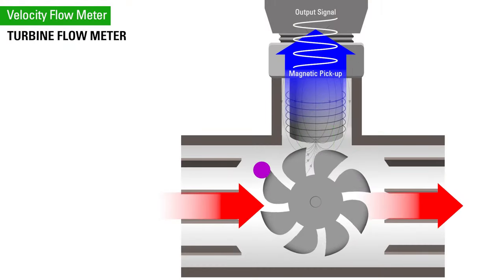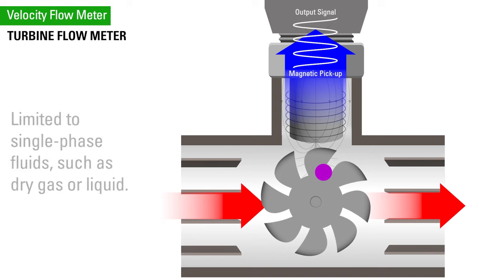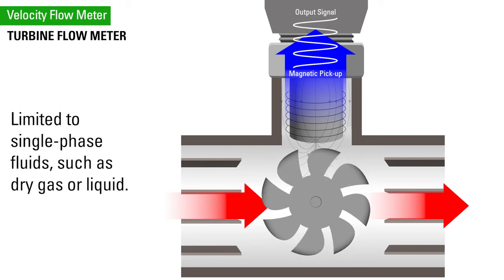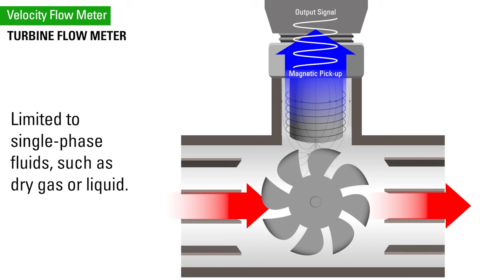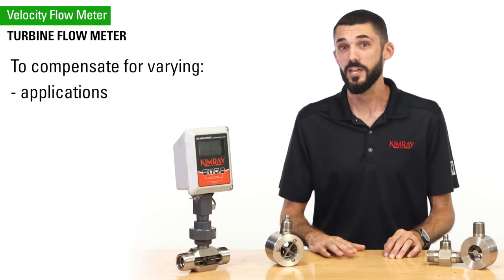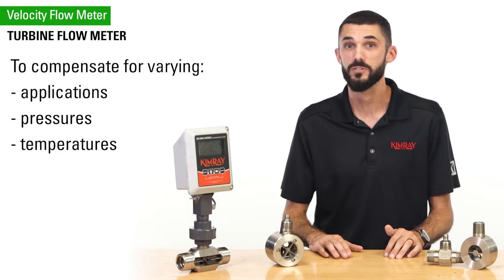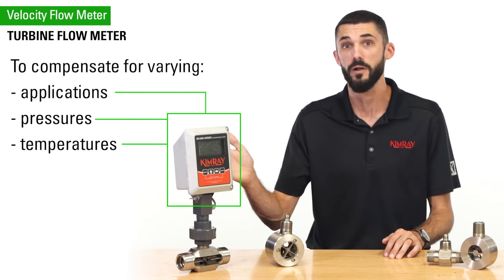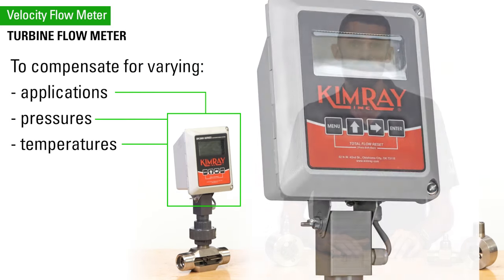Because of the moving parts and the operation, turbine meters are limited to single-phase fluids such as dry gas or liquids. To compensate for the varying applications, pressures, and temperatures, those variables must be accounted for in the flow monitor to calculate an accurate measurement.